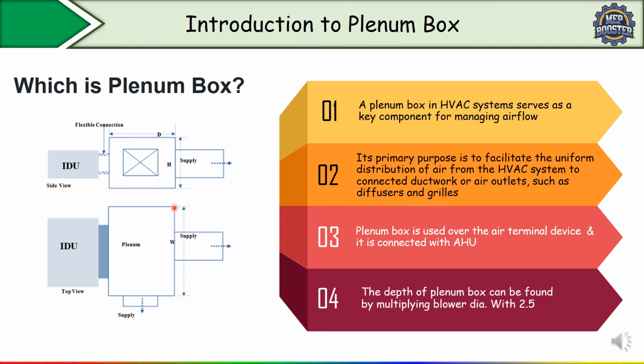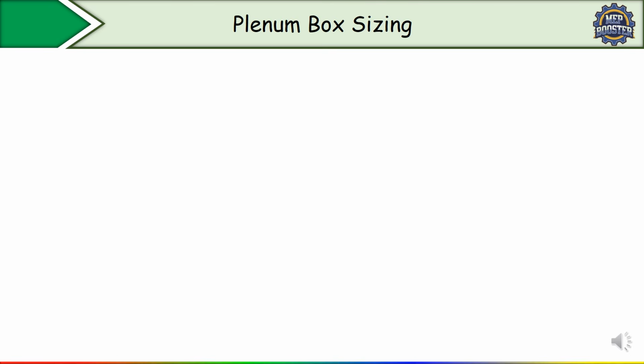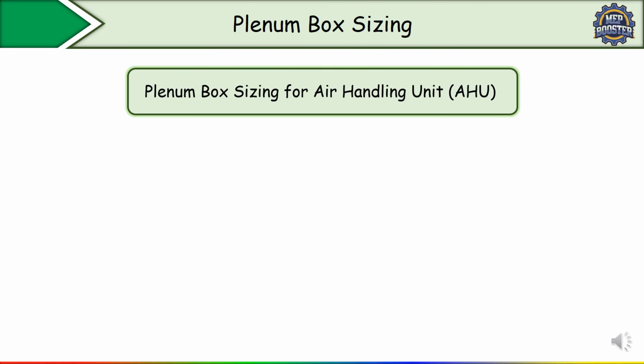And now the next point is given here. The depth of the plenum box can be found by multiplying the blower diameter by a 2.5 factor. So if you want to find out the depth of the plenum box, you have to multiply the blower diameter, which you will get from the manufacturer, by this 2.5 factor. Now we'll show you the plenum box sizing for the air handling unit.